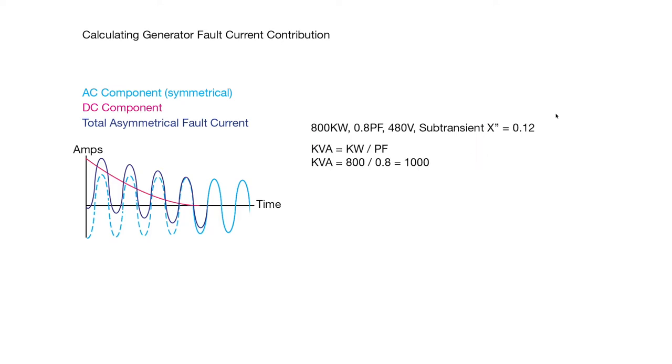So first we need to calculate the kVA, and we do that by just dividing the kW by the power factor, so we get a 1000 kVA generator.